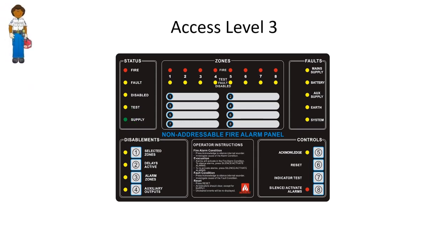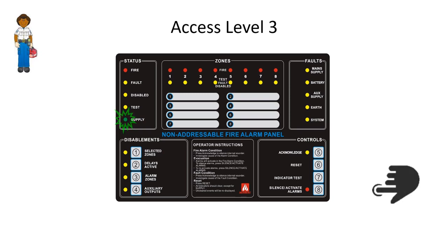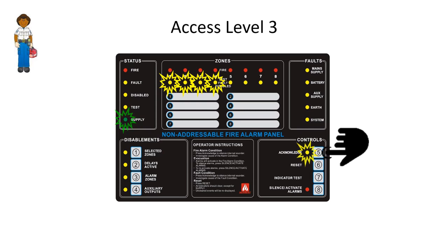To enter Access Level 3, again, check that there are no unacknowledged events on the panel, then press the Acknowledge button for 3 seconds. The supply LED will flash rapidly. Now you can enter the Access Level 3 passcode. Press 8765. Press the Acknowledge button to confirm the passcode.